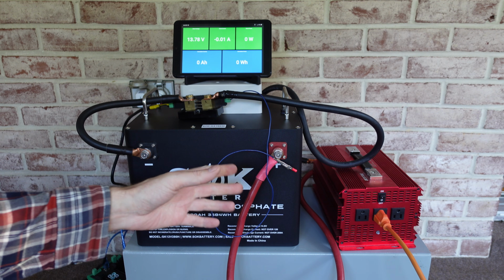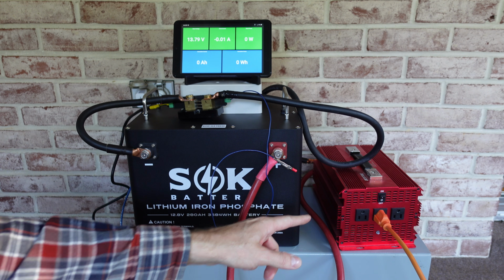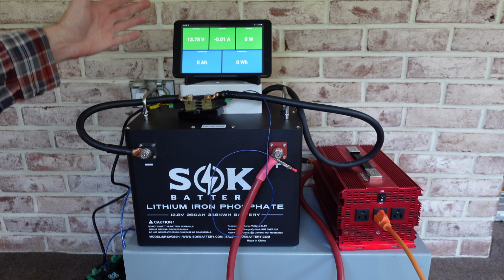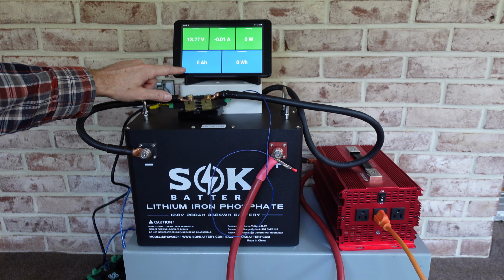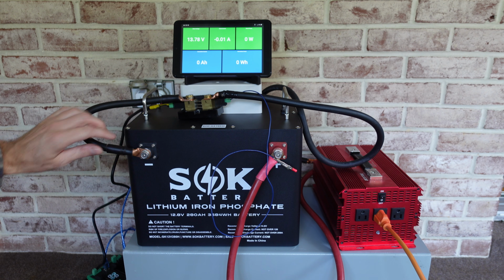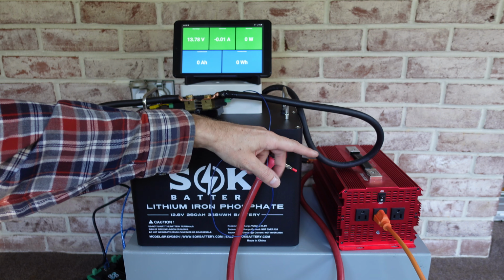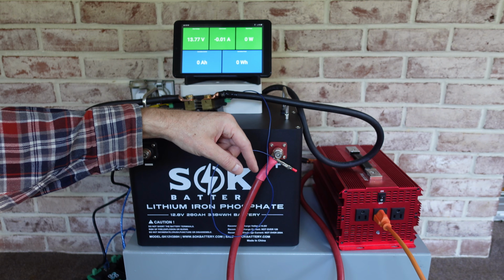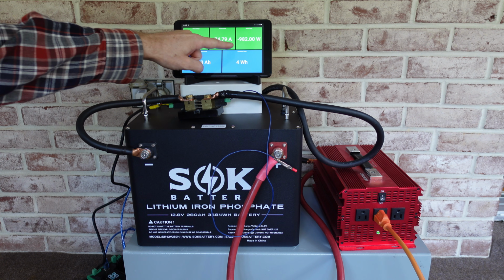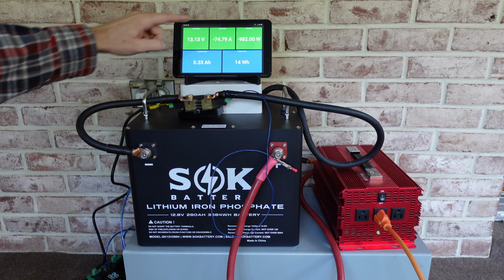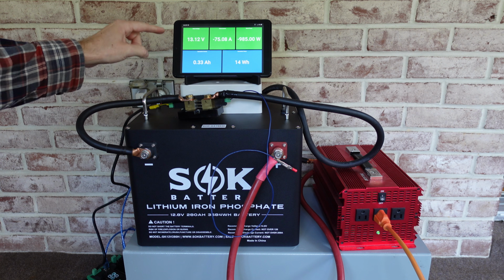I have my usual capacity testing setup connected: a 12 volt inverter, and a Batrium shunt in my display. We can see on the bottom here discharged amp hours and discharged watt hours. My test load is the AIMS 48 volt charger going back to my server rack batteries, so we're sitting around a 982 watt load, approximately 75 amps at the current voltage.